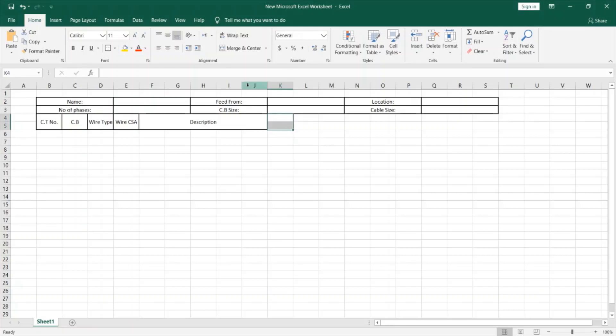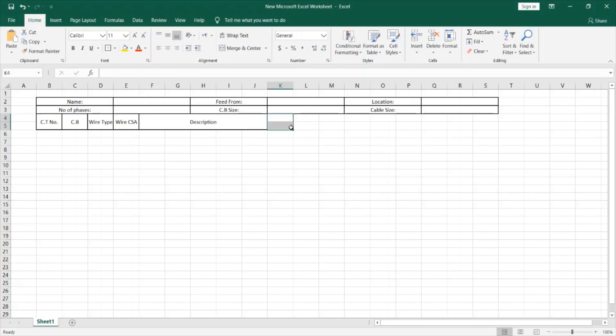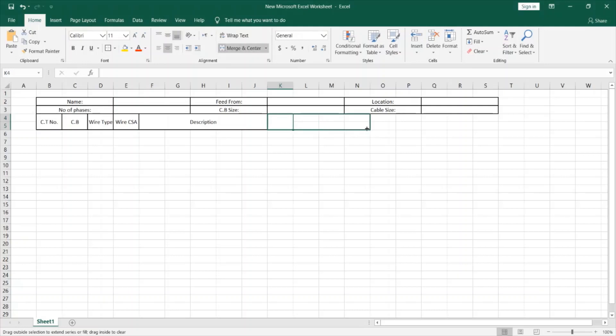Now I have to define the loads. Although I can make just one load which includes the lighting and power and all loads in just one cell or one column, but always it's preferred to choose or to segregate the loads into different loads like the lighting to be separated, power sockets, water heaters, air conditioners, and other loads. So what we will do is we will merge this cell and give it a border. Then we will make the other loads in a separate cell as well.